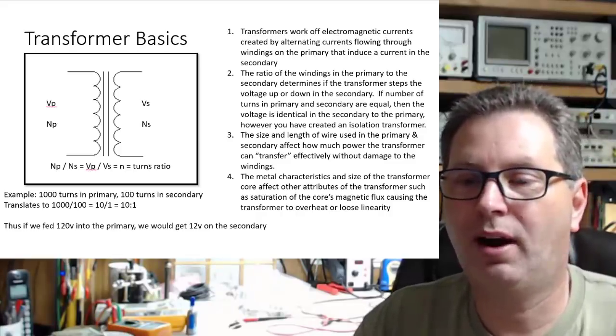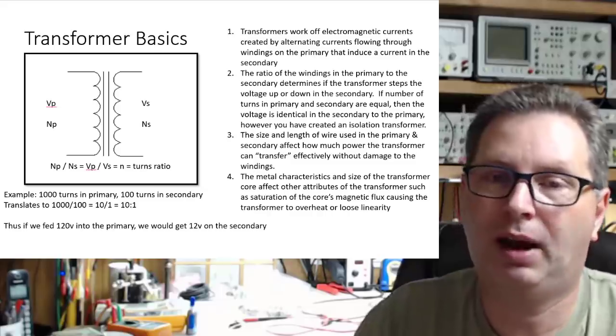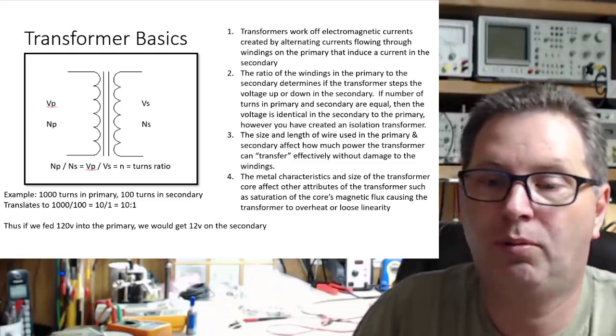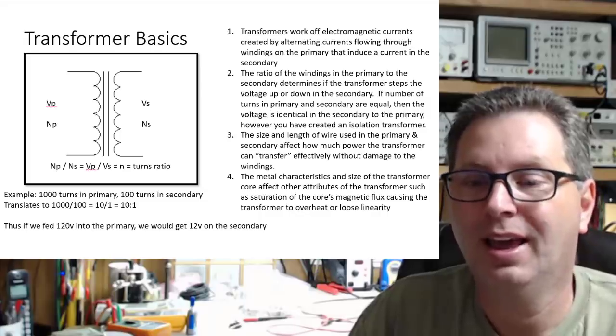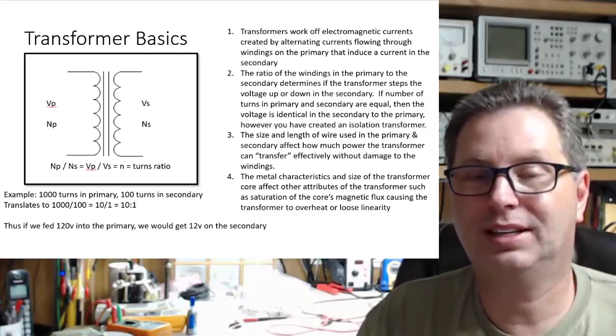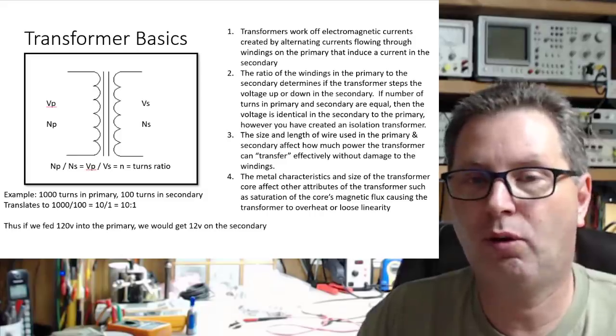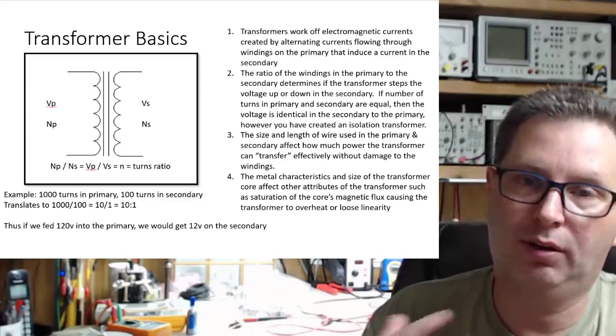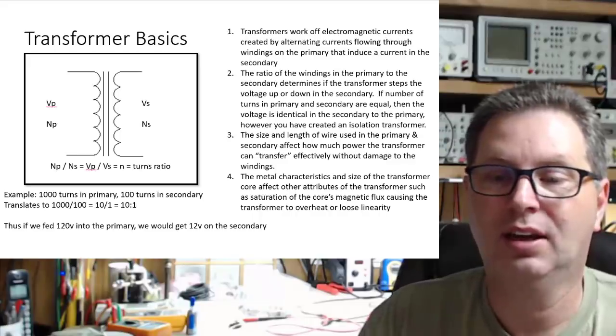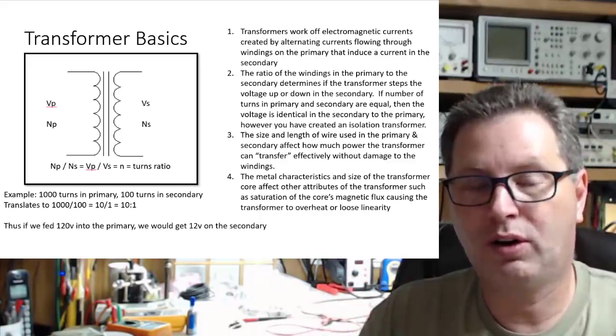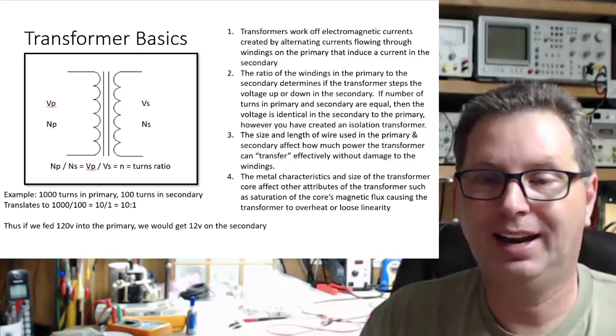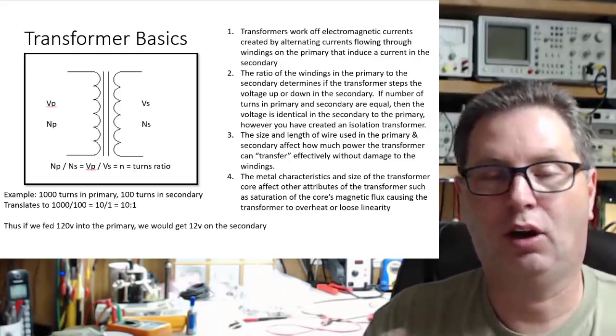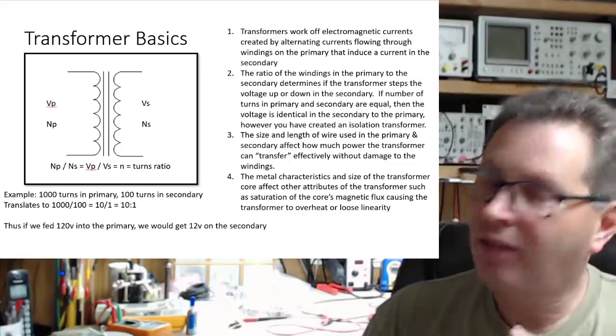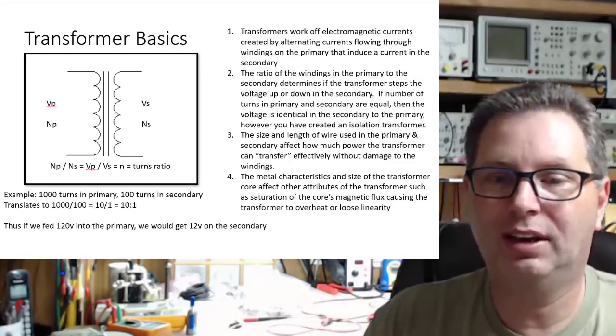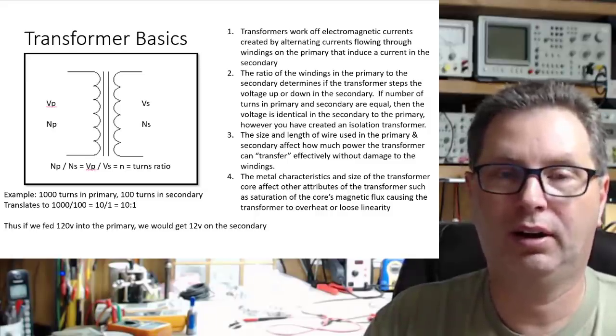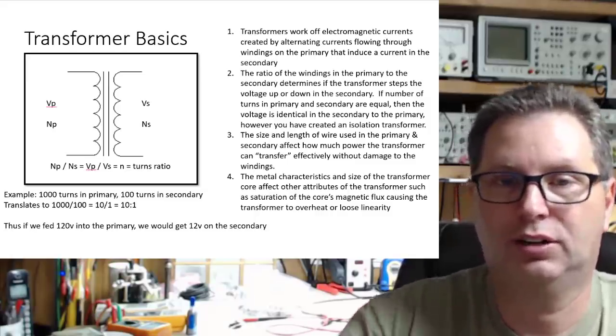The size and length of wire used in the primary and secondary can affect how much power the transformer can handle without damaging the windings. The metal characteristics and physical size and shape of the transformer and core also affect its efficiency, and how easily the core saturates with magnetic currents, causing it to overheat or be less efficient. So there's a lot more to transformers, but for today's video, all you need to understand is the windings ratio I talked about.